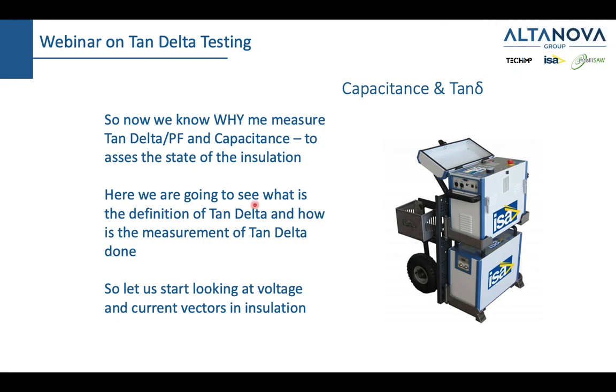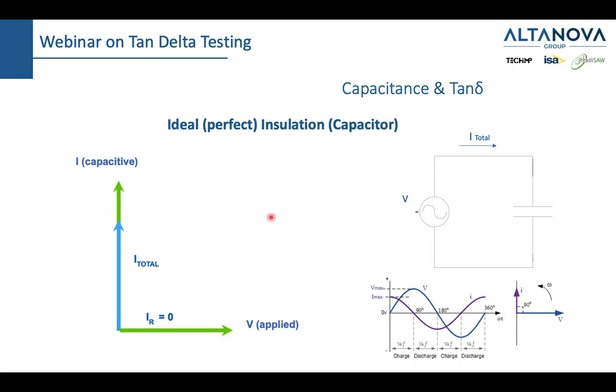But let me say that we will also talk about some other names for tan delta. You will see that another name for tan delta is dissipation factor, while the concept of power factor is being used in some other countries, for example, the USA, etc. So let us start now looking at the voltage and current vectors in an insulation. In an ideal insulator, in an ideal capacitor, we have a 90 degree shift between current and voltage. So this is the voltage which we apply, and this is the current which is caused by that voltage.